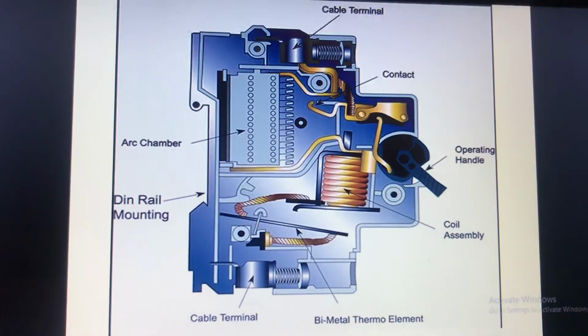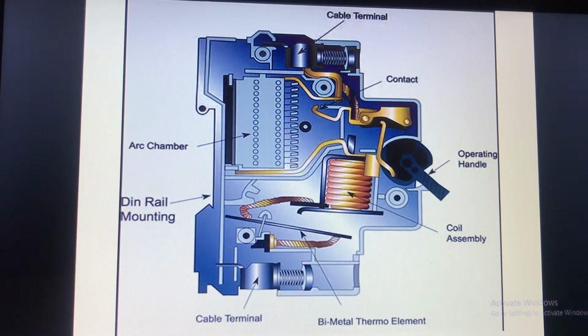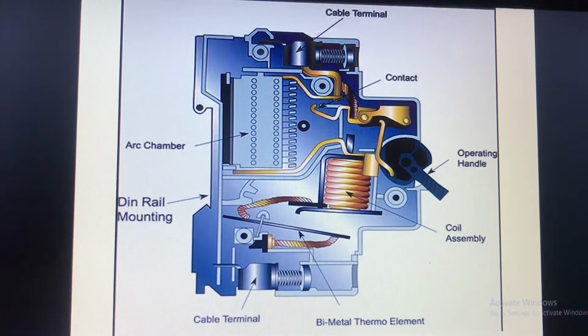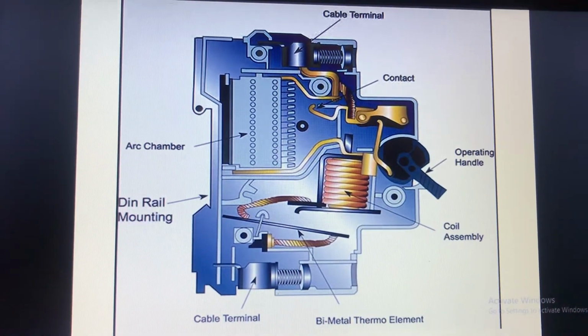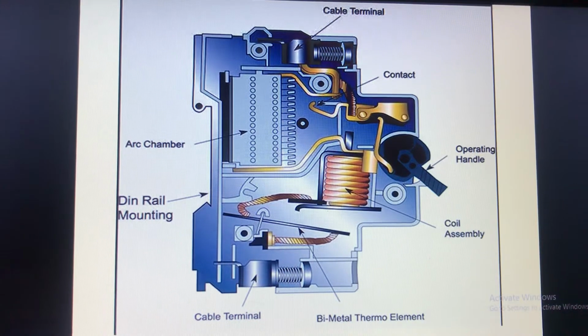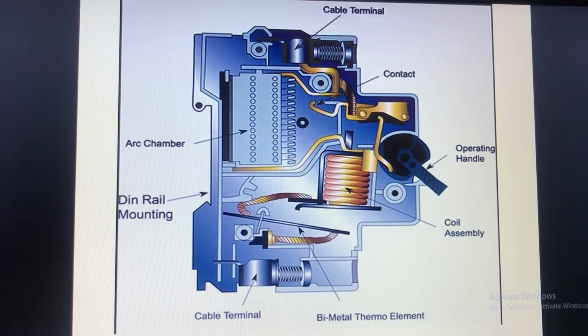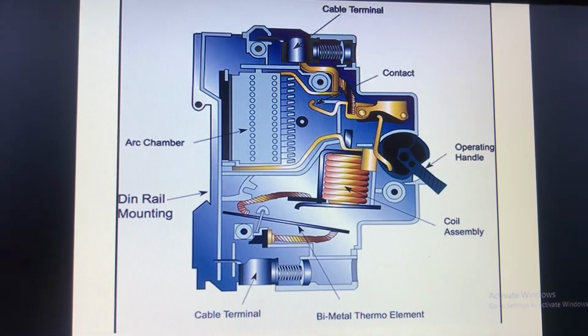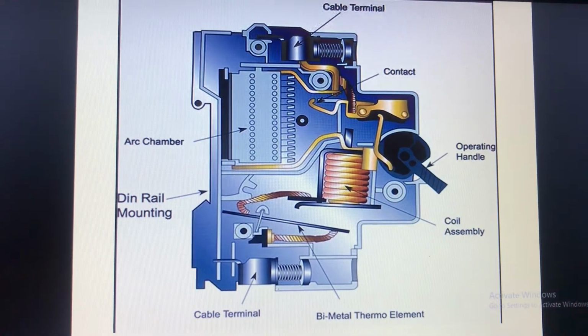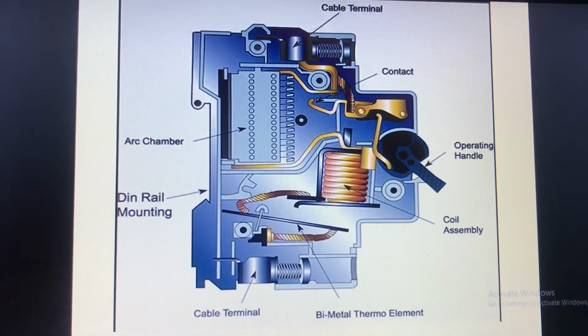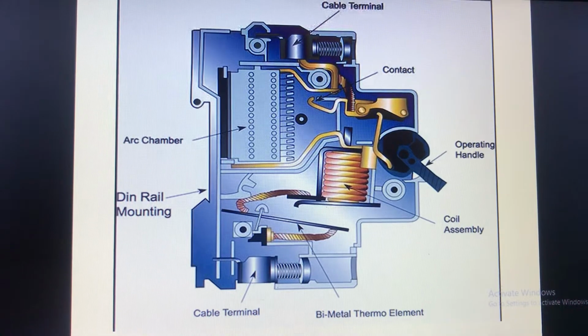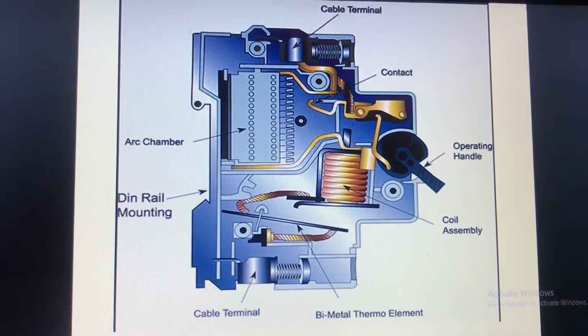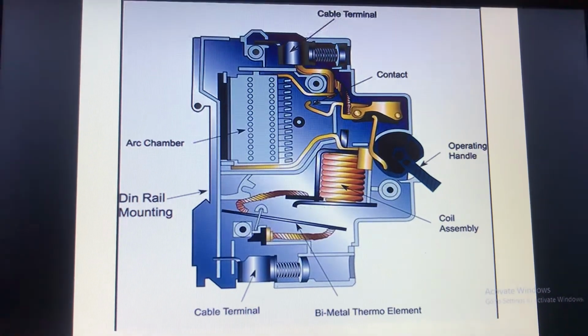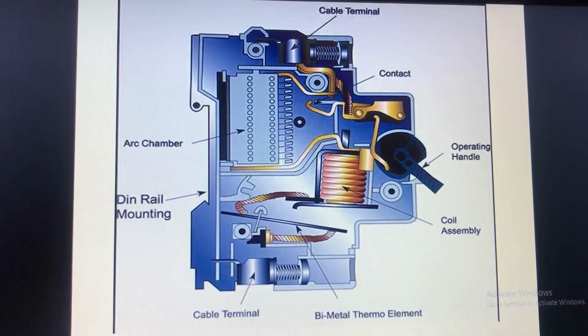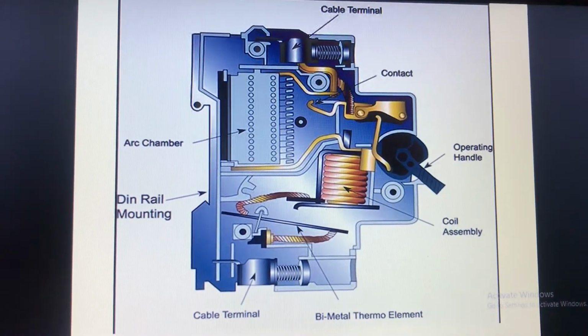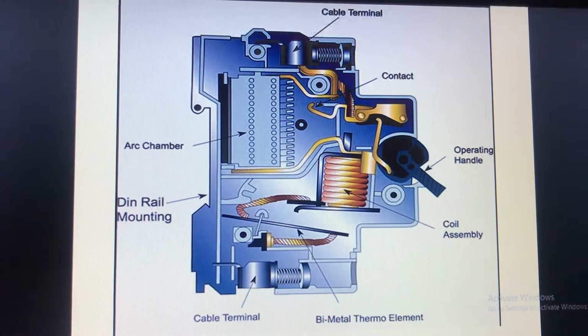So here you can see its diagram. So it's the cable terminal input at the top, you can see it's the cable terminal, and then the contacts. So it will make or break accordingly, and then is the operating handle. You can operate it manually and use it as a switch, and automatically it will operate when there are short circuit or overloading in the circuit. So then is the coil assembly, that is electromagnetic relay. This coil assembly or electromagnetic relay works when short circuit occurs. Bimetallic strip, it functions when there is overloading of the circuit.